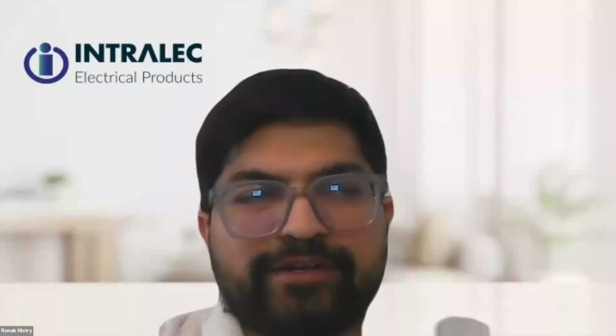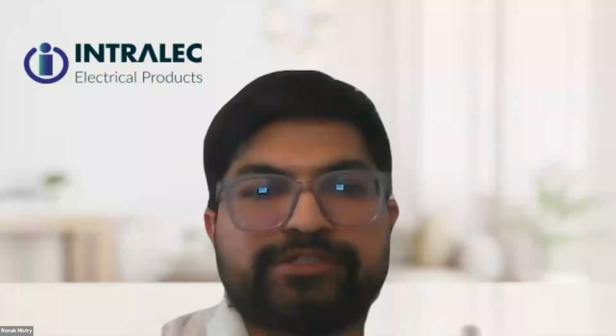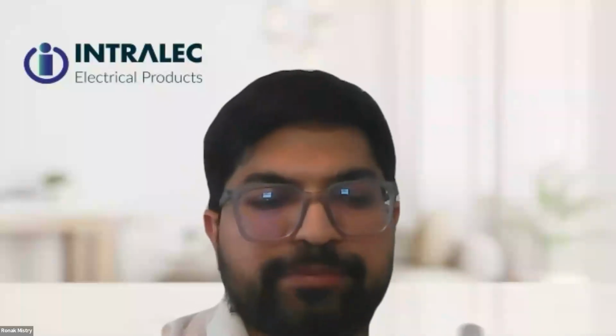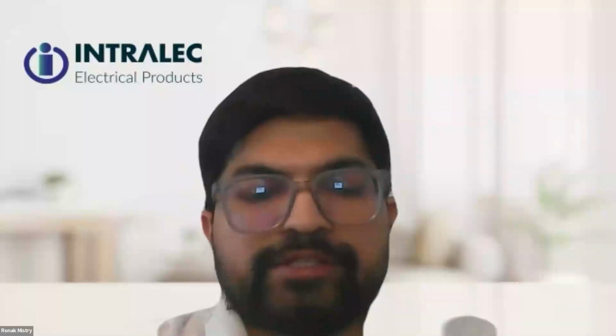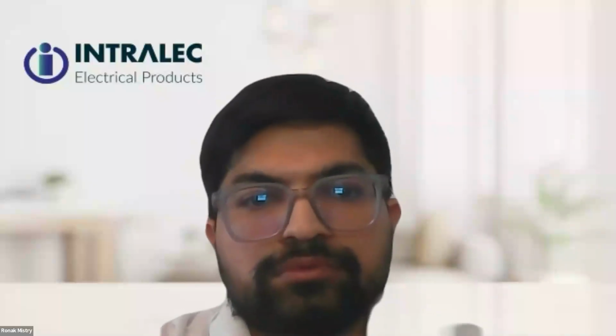Thank you. Mario, I have a question for you regarding the transformer specifications. You had a slide regarding how the engineer and consultant should specify a transformer. So, in your experience, what are the most common transformer specification mistakes in solar or battery energy storage systems? The mistake we see the most is the core construction, because they're going to specify, let's say, a YY, but they won't specify a 4 or 5 legged core. Everybody wants to win the job, so everybody wants to provide the quote with the most cost-effective pricing. So if you don't specify the proper core, of course, a 3-legged standard transformer YY will be more cost effective than a 5-legged core. So that and the K factor are the most common omissions that we see on specs.